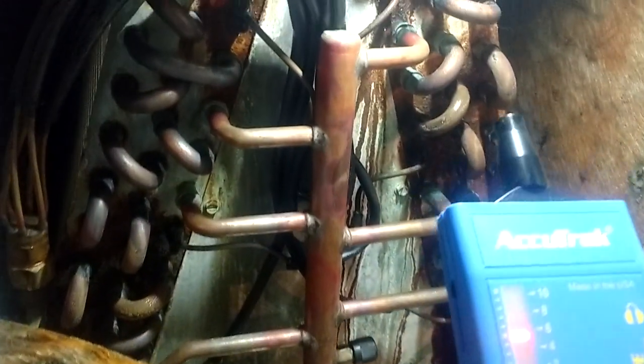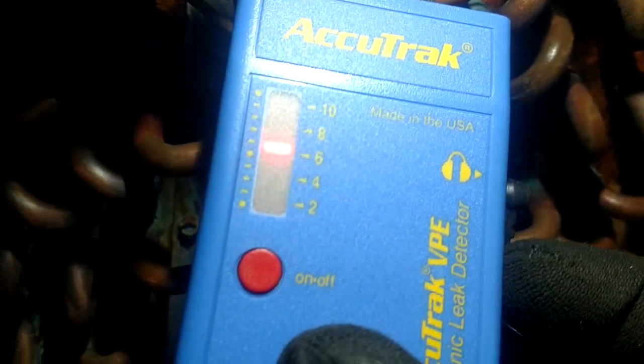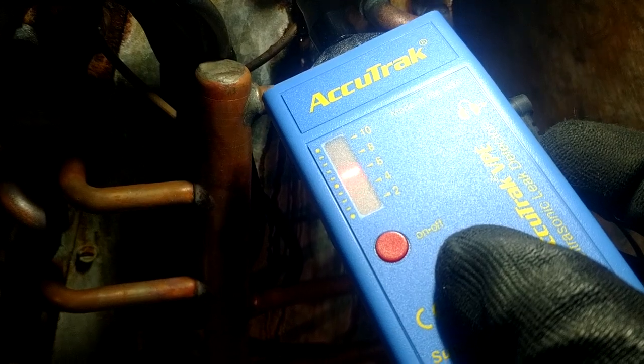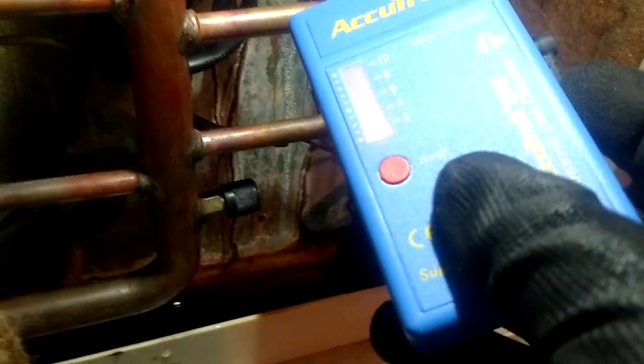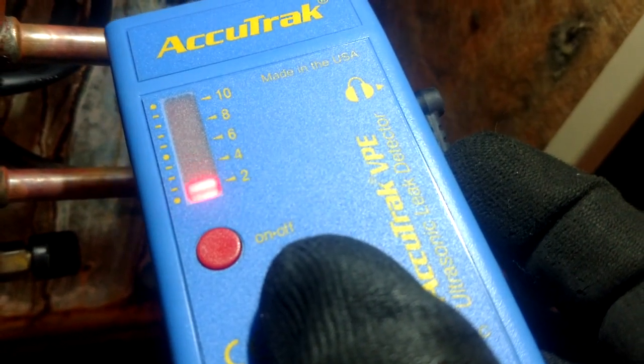I've got out the AccuTrak ultrasonic here and I found a couple of leaks — the main ones are around the feeder tube right up here. You can see that if I move away it goes away. There wasn't anything in the back, but when I come back over here and get closer you see it start going up, so it's right in there. The one underneath it was leaking just a little bit, and I got another hit down here in the bottom corner.